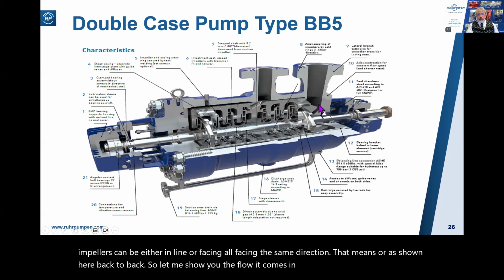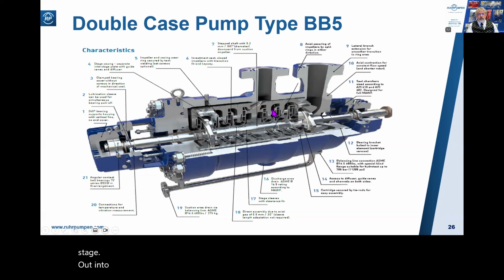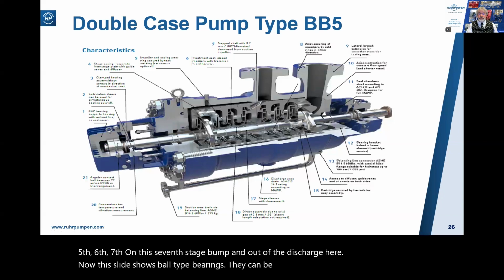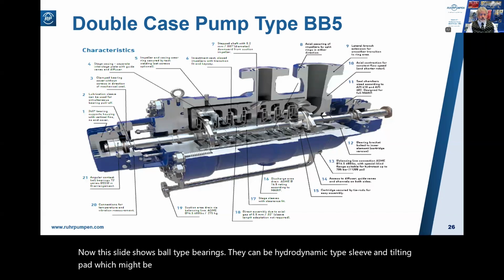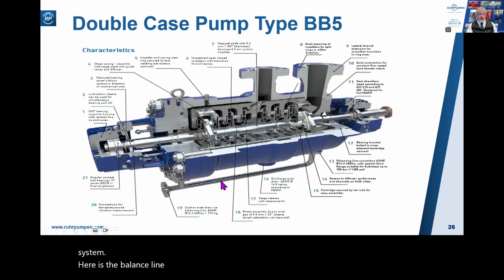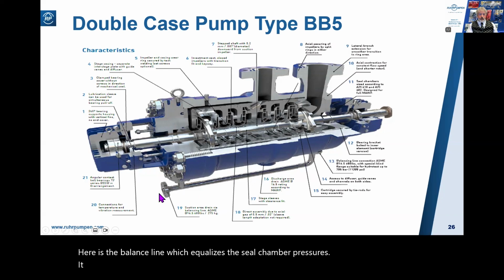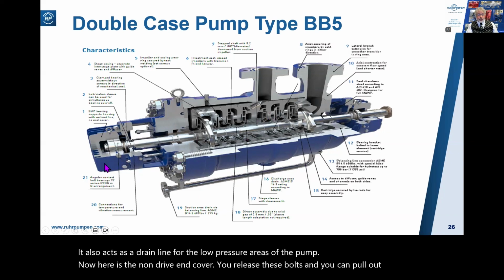So let me show you the flow. It comes in here at the suction, into the first stage, out into the second, into the third. From that one, it comes into this crossover, back here into the fourth, fifth, sixth, seventh on this 7-stage pump, and out of the discharge here. Now this slide shows ball type bearings. They can be hydrodynamic type, sleeve and tilting pad, which might be required on larger pumps, and these would require a separate lube oil system. Here is the balance line, which equalizes the seal chamber pressures. It also acts as a drain line for the low pressure areas of the pump. Now here is the non-drive end cover. You release these bolts and you can pull out the inner assembly, the cartridge, in this direction.